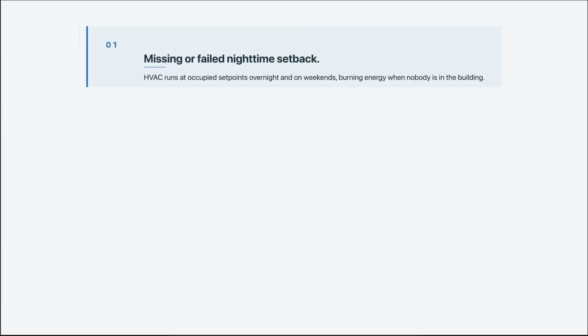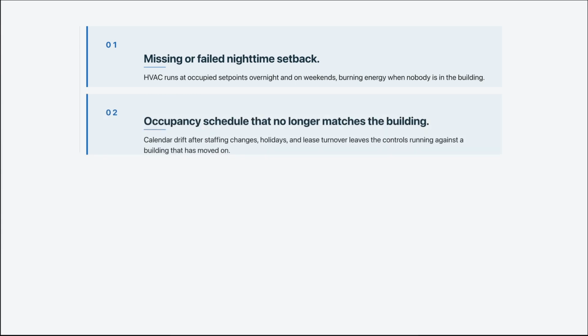Here are some examples of what building owners consistently find in the first month of continuous monitoring. Number 1, a missing or broken nighttime setback. The system's supposed to change to a different temperature overnight when the building's not being used, and it doesn't. Maybe it hasn't for longer than anybody remembers, and that's costing you money. Number 2 is an occupancy schedule that no longer matches how the building is used. Maybe a tenant added evening hours several years ago, and the HVAC is still assuming 9 to 5.